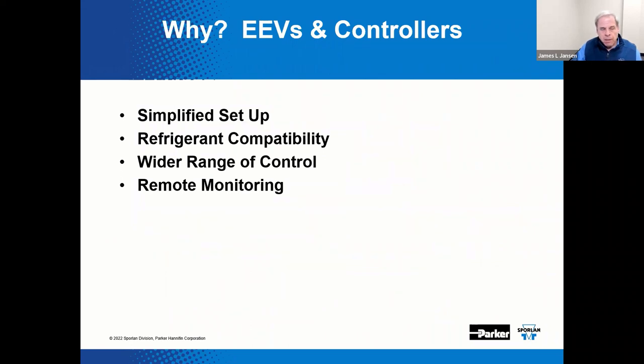Before we go any further, I think it is worthwhile to consider the use of these electric valves and the necessary controls. The commissioning process is much simpler — key in the selected parameters and you're ready to go. The process to set superheat is potentially much more time consuming with the mechanical thermostatic expansion valve; there's no need to unload the case. If a refrigerant retrofit is performed, there's generally no need to change components, provided the control in place accommodates the new refrigerant. The control rate range is significantly wider compared to the mechanical version, with less sensitivity to changes in weather and load.